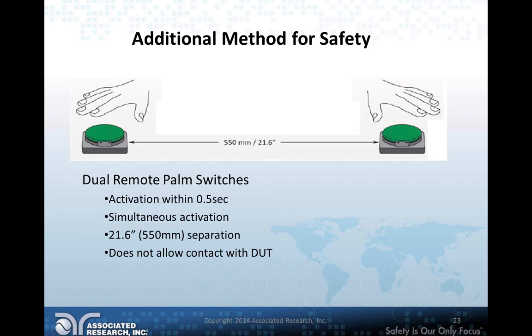You also want to separate them by at least 21.6 inches. What that allows for is that somebody can't cheat and use the same hand to activate both switches—for example, putting your elbow on one switch and then reaching your hand over and putting it on the other switch.